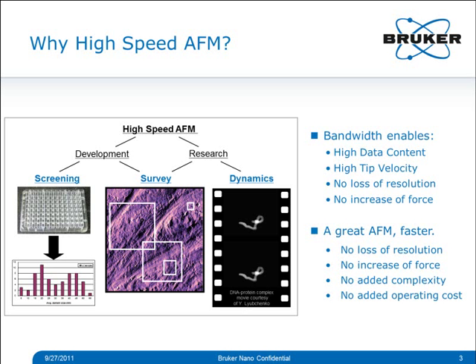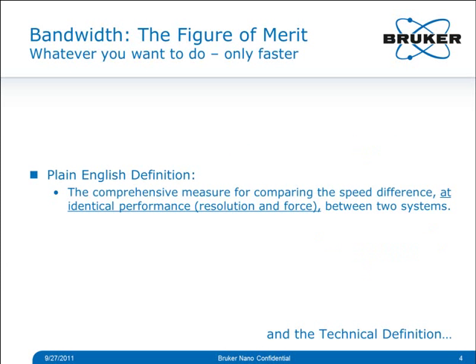Now let's talk about bandwidth. Many different ways have been used to describe speed improvements in AFM: frames per second, lines per second, cantilever resonance frequencies, laser spot sizes — all related to increasing AFM speed, but also confusing. From normal AFM we know that maximum imaging speed depends greatly on the sample, mode, scan size, set point, and image quality. We find the most comprehensive way to compare AFM speed is to compare, for any specific sample at the same mode, scan size, tip-sample interaction force, and image quality, how much faster one system images than another. We call this ratio the improvement in imaging bandwidth.